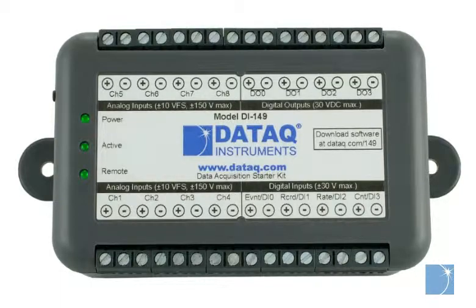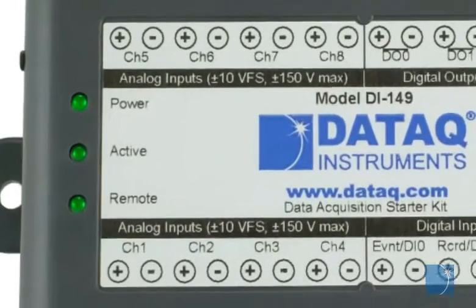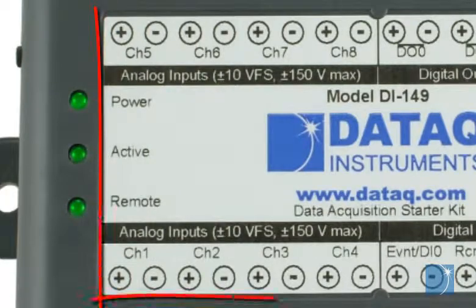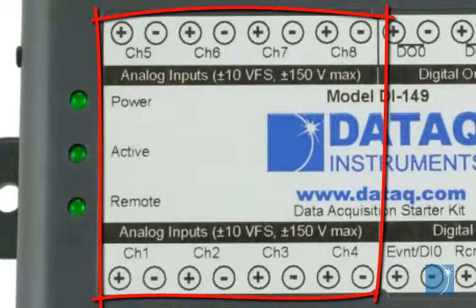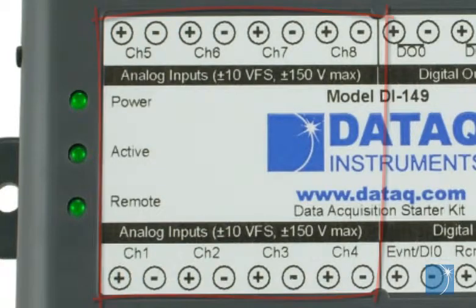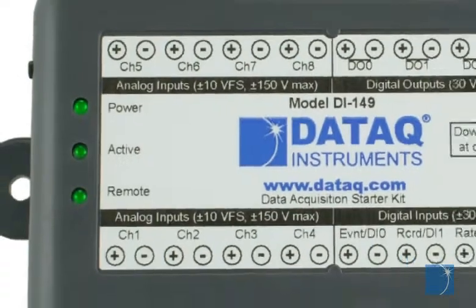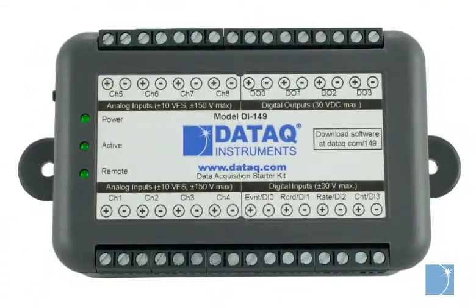The DI149 is an 8-channel USB connected data acquisition system. The 8 fixed differential inputs have a plus or minus 10 volt full scale measurement range with 10-bit resolution and overvoltage protection up to plus or minus 75 volts continuous or 150 volts for up to a minute.